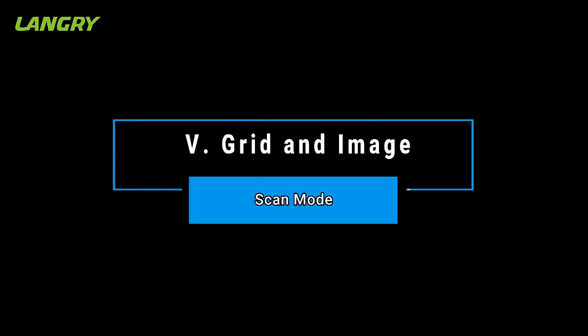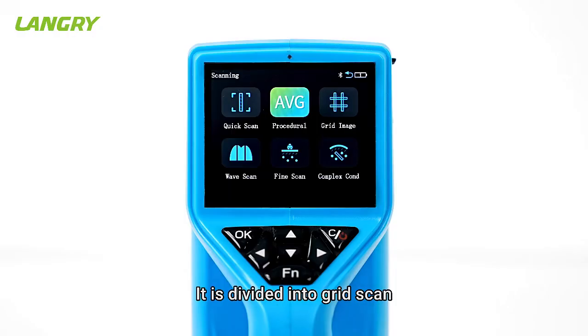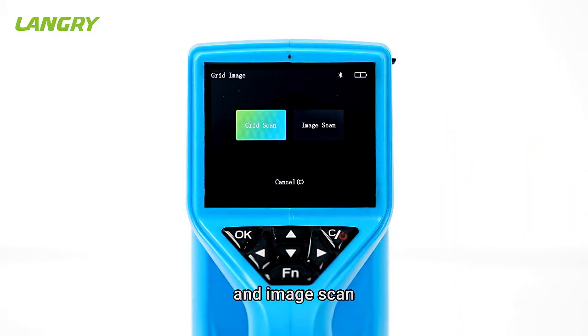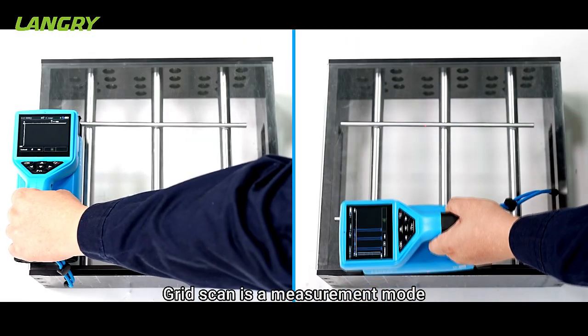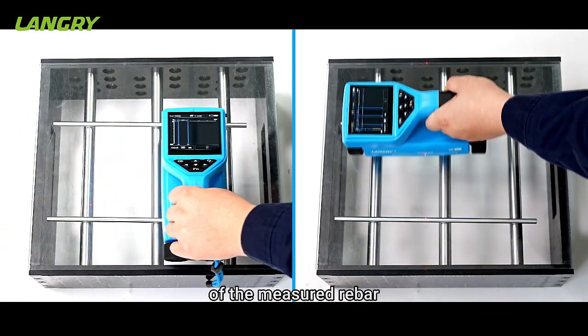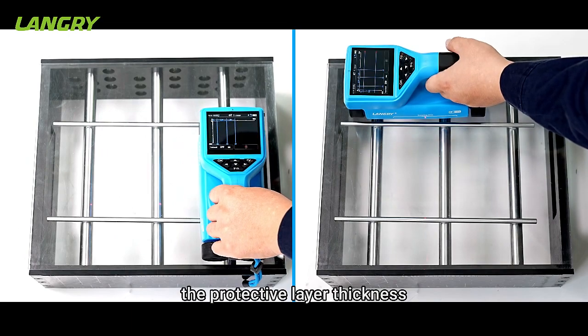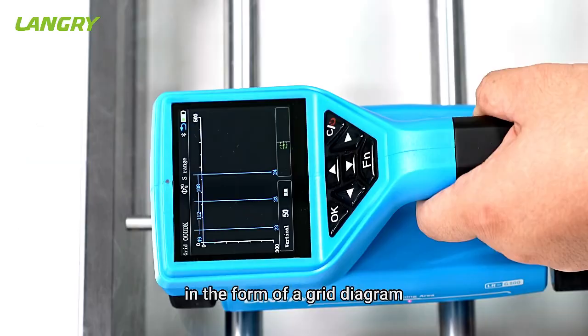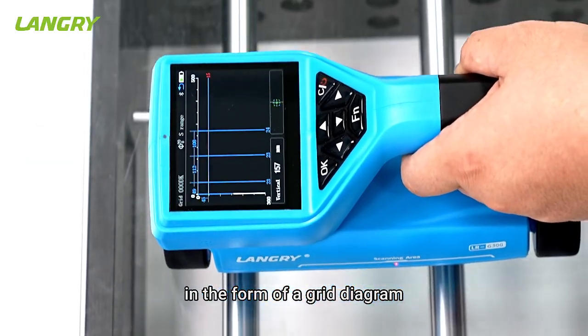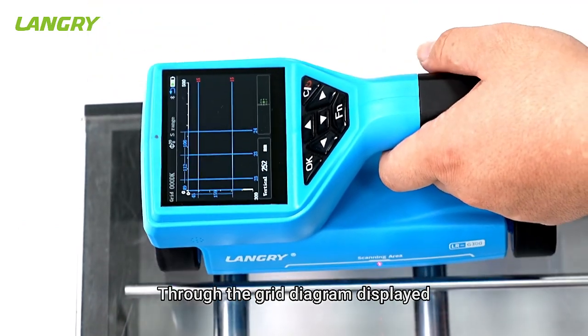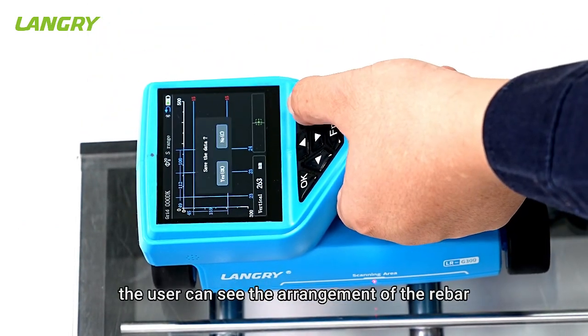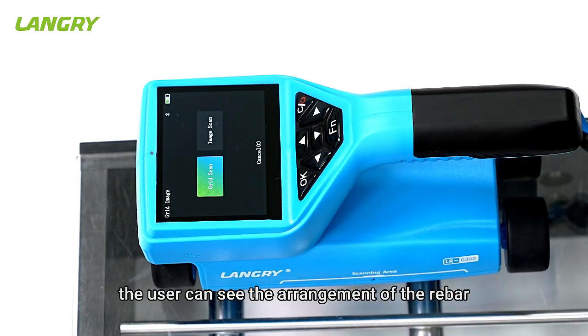Scan Mode 5, Grid and Image. It is divided into Grid Scan and Image Scan. Grid Scan is a measurement mode that displays the position of the measured rebar, the protective layer thickness and the rebar spacing, in the form of a grid diagram. Through the grid diagram displayed by the grid scan, the user can see the arrangement of the rebar.